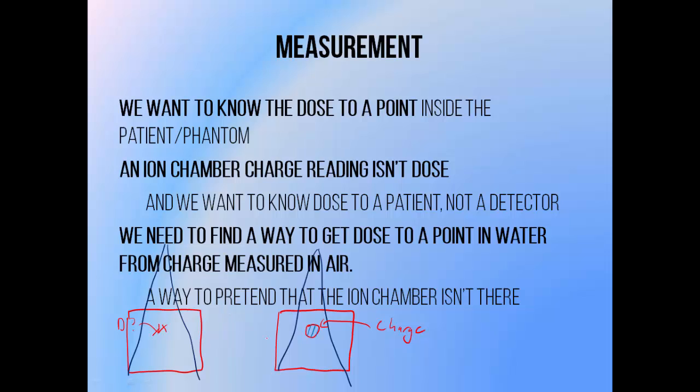The charge isn't dose, and a measurement obtained inside a detector volume isn't the same as what we'd get inside a phantom if the detector wasn't there. We need to be able to convert this charge reading into dose to a point.